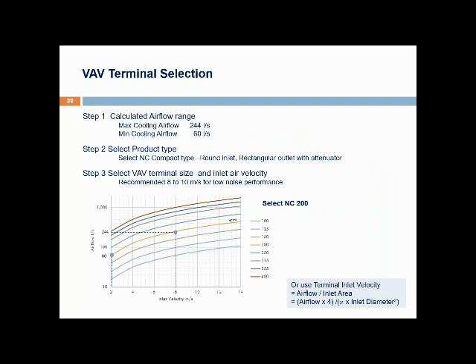Continuing the earlier example to complete the unit selection: Step one — the calculated airflow range is maximum cooling airflow of 244 L/s and minimum of 60 L/s. Step two — select the product type: a compact type, round inlet and rectangular outlet, with internal insulation for thermal insulation and acoustic attenuation. Step three — select the VAV terminal size. Based on the recommended 8 to 10 m/s and the chart shown, we select model NC200 with a maximum airflow of 244 L/s at an air velocity of 8 m/s. Alternatively, the unit size can be found by calculation using the relationship between airflow, air velocity, and area.